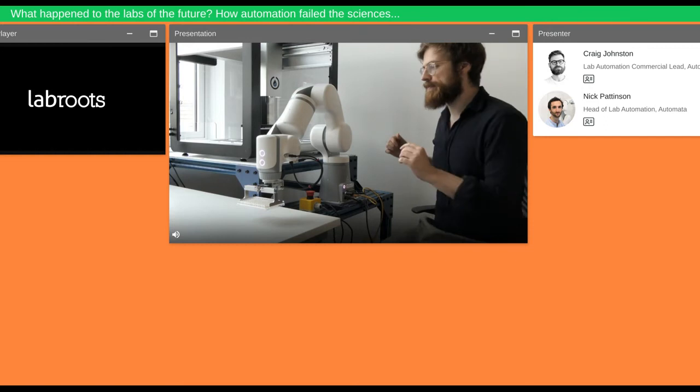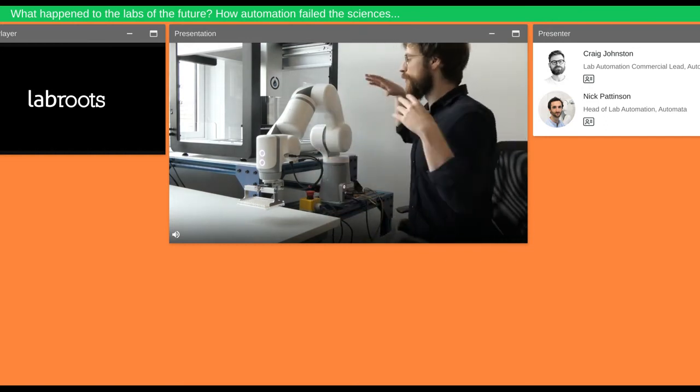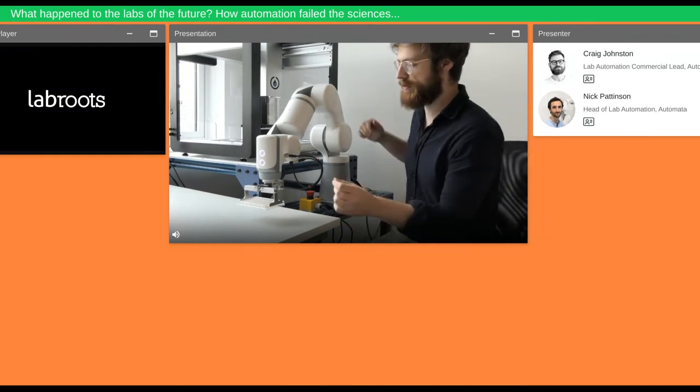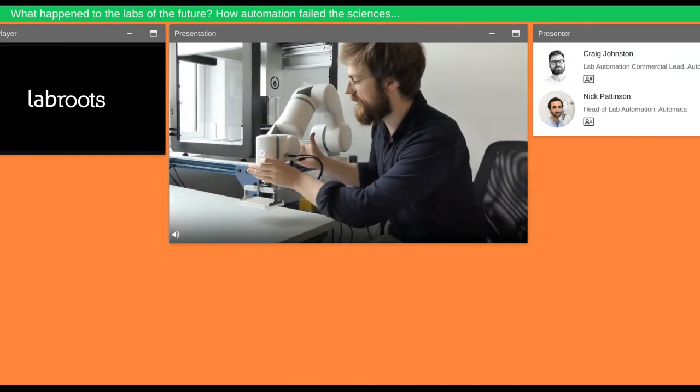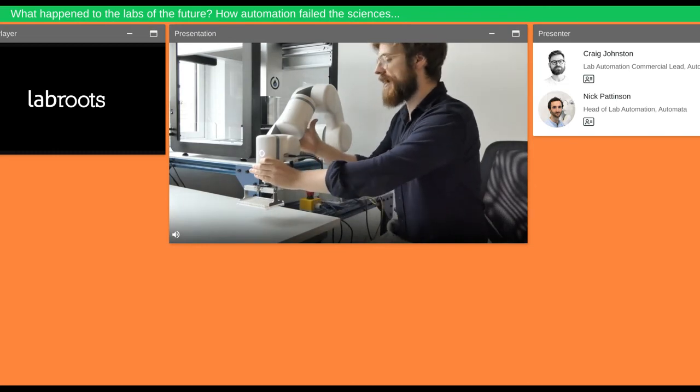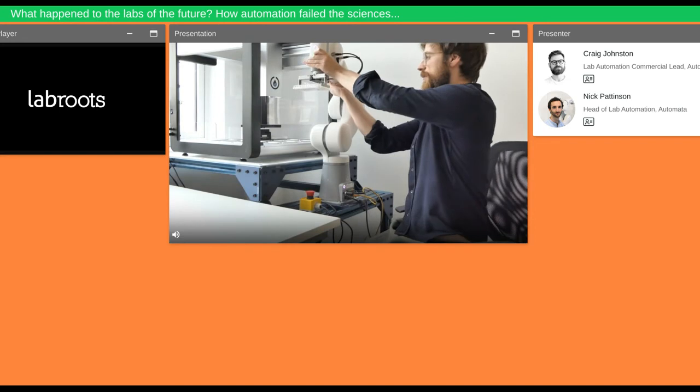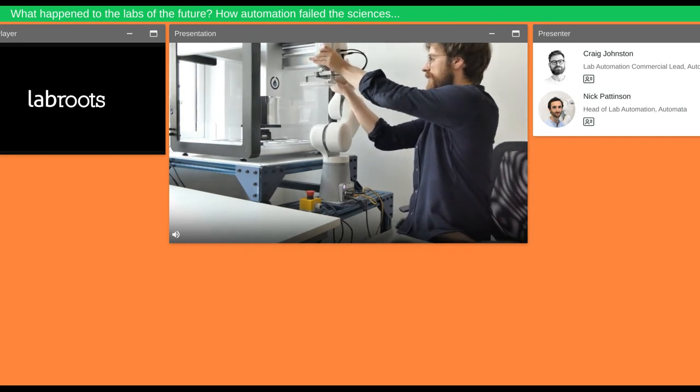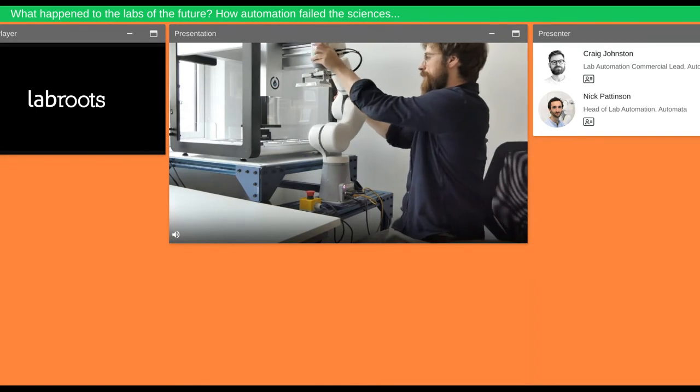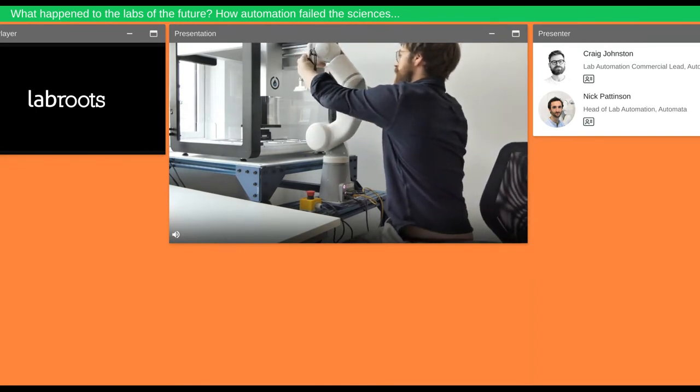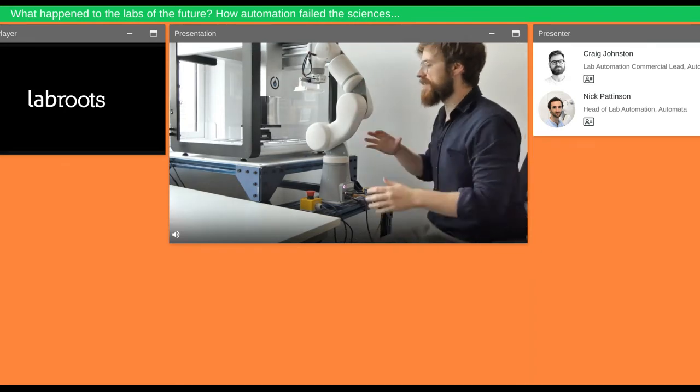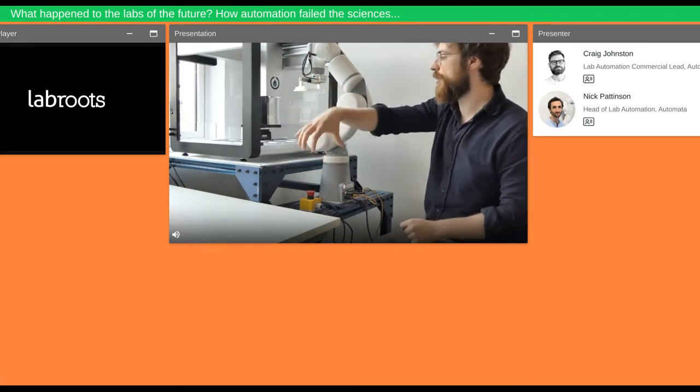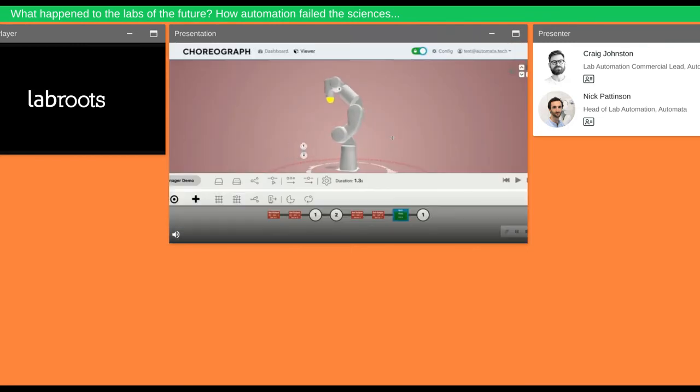So whenever we pick something up, it's always good practice to put a wait in. And that's just going to be of 0.2 seconds there. And the last thing that we're going to do is make sure that at the start of every toolpath, our gripper jaws are open. So all I'm going to do is basically set the reverse of what I've set here at the start of the toolpath. So end effector digital one to one, and end effector digital two to zero. And that means every time we start, the gripper's in the right position for us to pick up that microplate. All we need to do now is upload that toolpath to the robot, hit home to go to the first position, and then hit play. So now that we've picked the microplate up, what we're going to do is program it to move around, over, and into the Opentrons. So I'm just going to do what I did earlier with the back driving, which is press down that button here. And we're going to guide it with two hands, so I want to make it easier. So we're going to bring it right back up in here, and we're going to save that point. And that means that the robot isn't going to swing around, we go right in, we've got a safe trajectory into the machine.